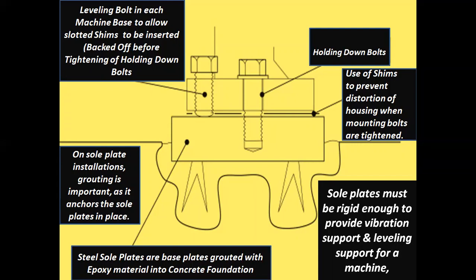Sole plates must be rigid enough to provide vibration support and leveling support for the machine. The diagram represents all accessories including bolts, nuts and shims. Steel sole plates are base plates grouted with epoxy material into the concrete foundation.